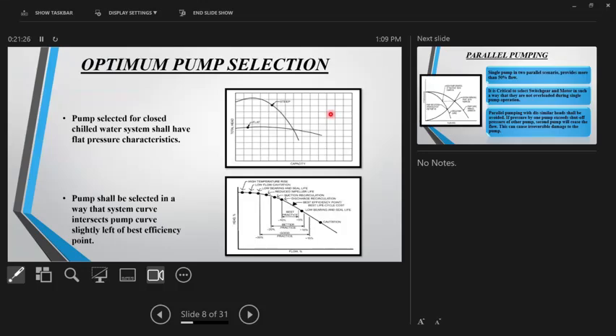One of the things is pump selection. Can we take care of this with pump selection? One of the recommendations from AECOM is that a pump selected for a closed chilled water system shall have flat pressure characteristics. What do we mean by flat? It's simple, it's geometry. Flat is flat. Steep is this. So the recommendation for closed chilled water systems, which is always the case, is that we should try to select the flat curve. The intent of a flat curve is that the variation in head is not appreciable with respect to flow. Here, your pressure gauge will keep on jumping. Here, you see the variation is not much, so your pressure gauge is not jumping that hard.